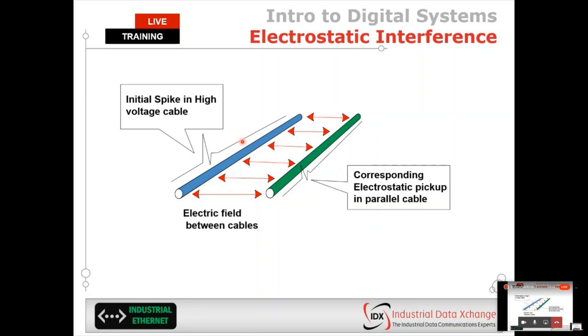When I talk about high voltage cabling, I love it when the high current or high voltage electrical guys jump on my courses, because they often argue with me about what high voltage is. I think in their context, high voltage is anything above 1.5 kV. In my context for industrial communication systems, high voltage is pretty much anything above 60 volts AC and DC. So anything above that voltage, you want to provide a separation from your industrial Ethernet cables. I'll talk a little bit later about what that separation requirement actually is.